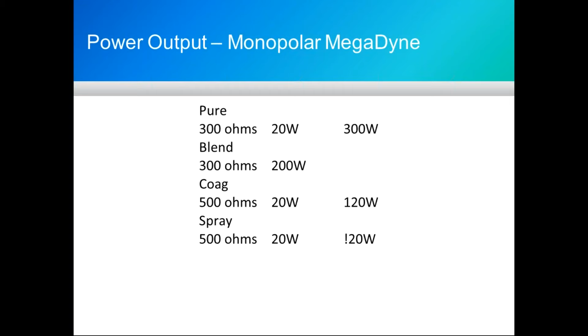Here's the Medtronic. They have several different cuts, and you go through all the different cuts, changing the ohms through it, and then you're looking for different outputs. And they're wanting the 10 to 20% for the output. Here's the Megadyne. This is the unit that we had pictured in the very first screen. It's a little bit more basic. You just go through the cuts and the coag with the different ohm settings, and you test it.